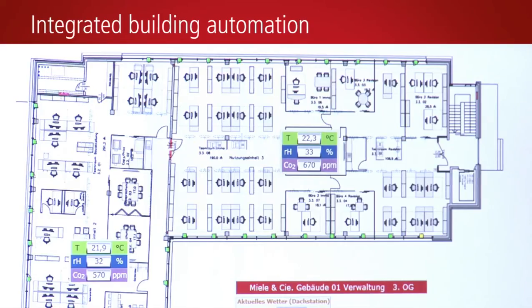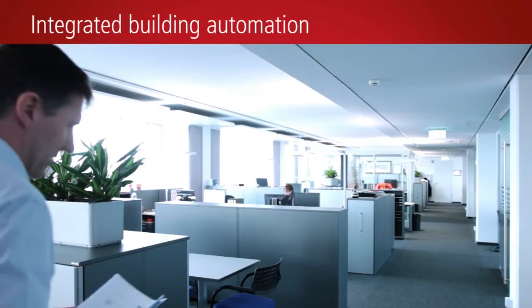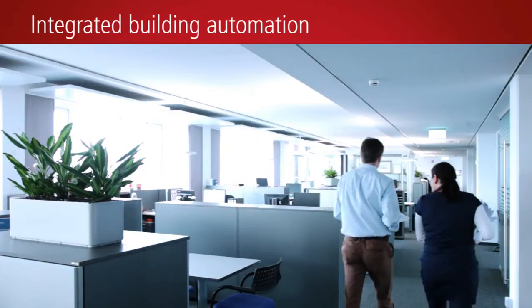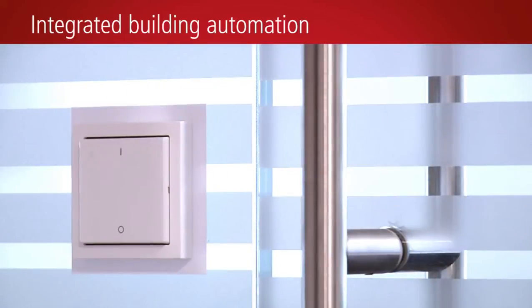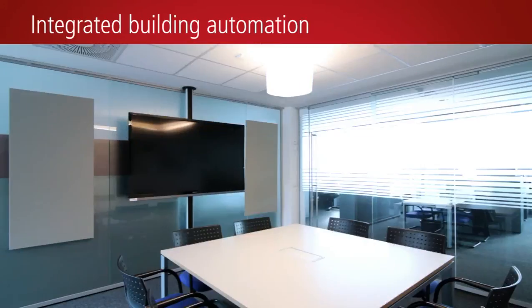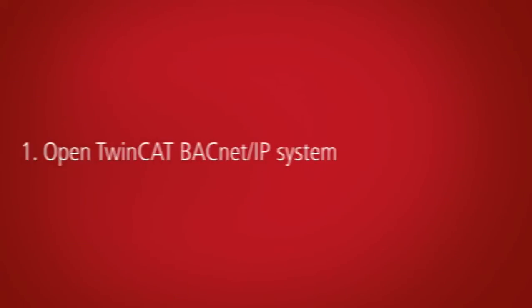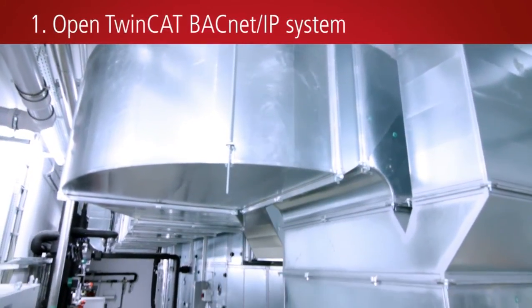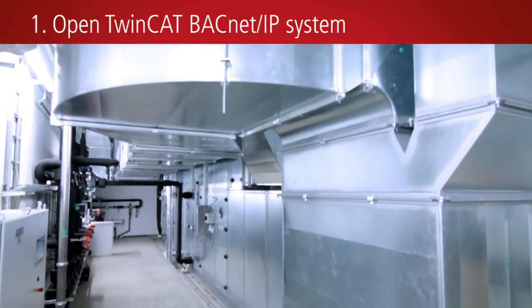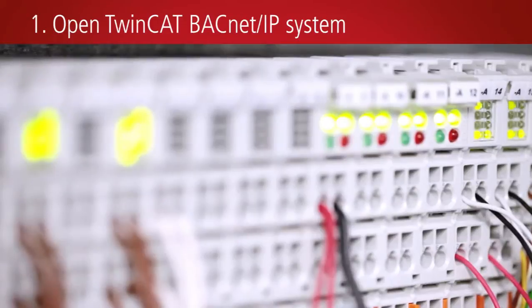A 15.6-inch multi-touch CP2916 control panel is used for visualization. TwinCat BACnet IP enables all subsystems to be integrated very easily into the overall system. The EnOcean wireless communication technology is much more flexible than a conventional wired installation. With the help of TwinCat BACnet IP, HVAC data along with room automation data can be mapped directly inside the Beckhoff embedded PCs.